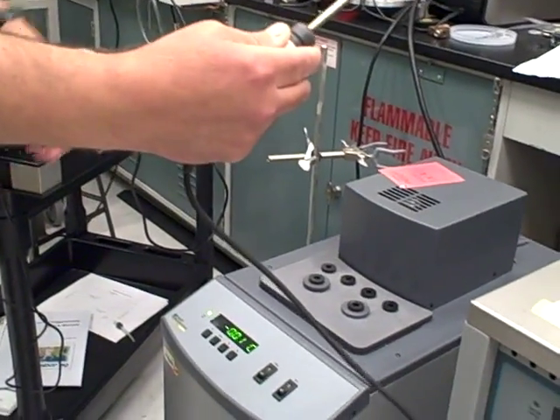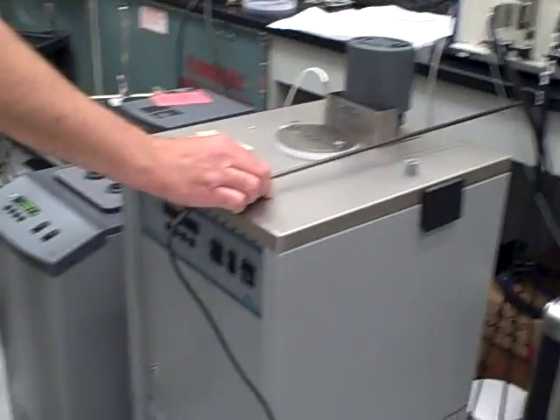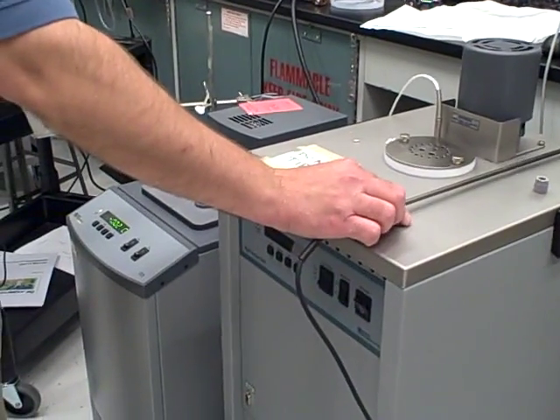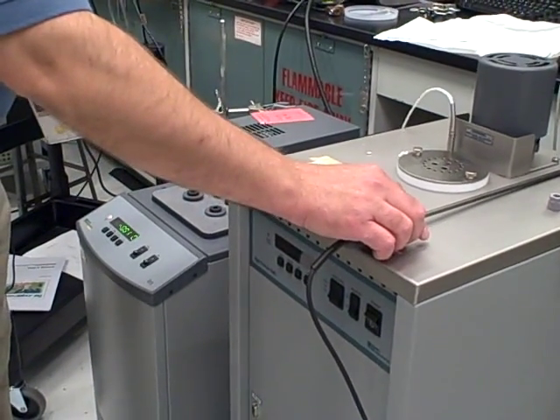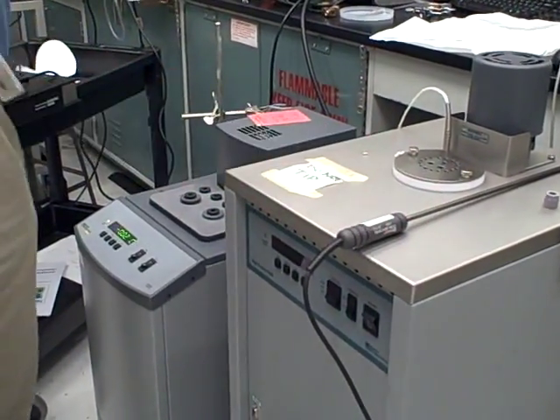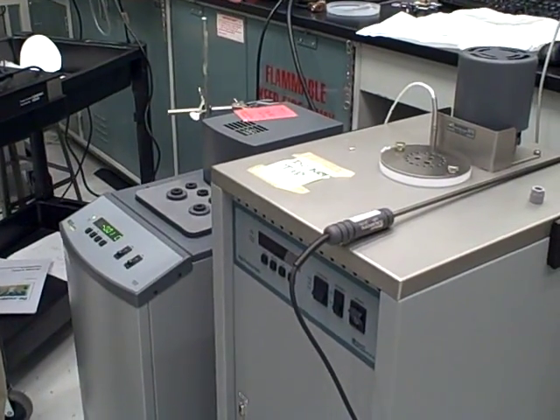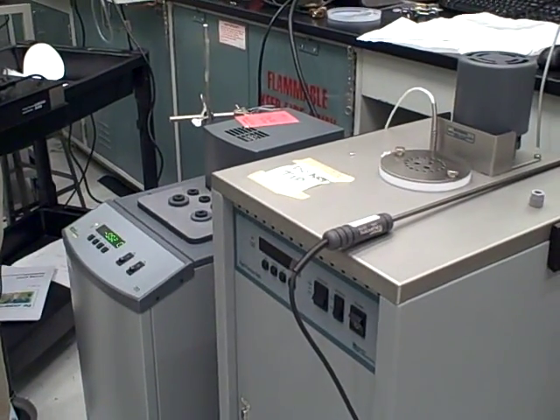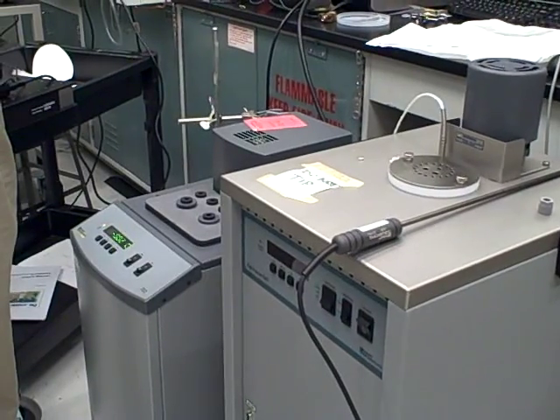So it's not very impressive, but it's our standard. Now, how do we calibrate it? Well, you have to calibrate it by using a known temperature. One of the known temperatures is the triple point of water, which is defined to be 0.01 degrees C.